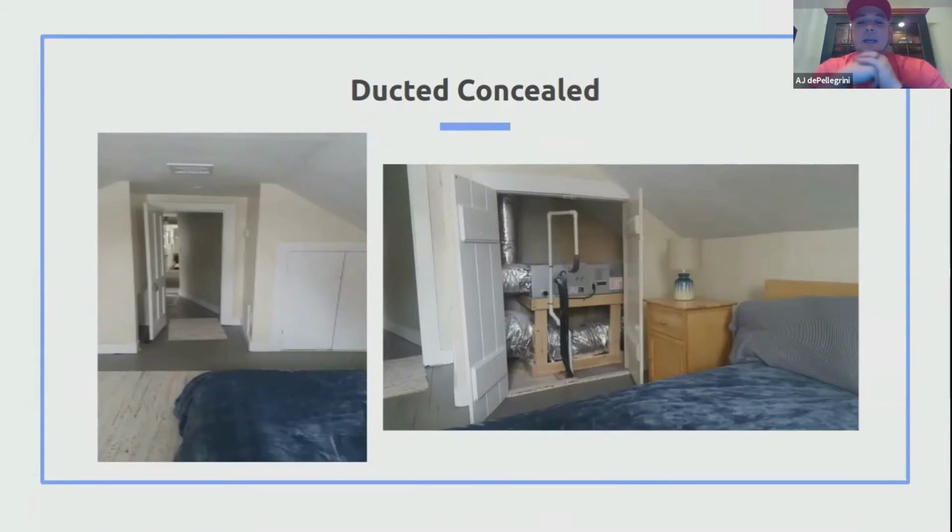This system here takes care of 3 upstairs bedrooms that are extremely hard to get to. The way that this works is a basic air handler with heat pump technology. So the coil can deal with hot or cold refrigerant, and it also works with the system. So it has variable fan speeds. It will modulate itself on refrigerant flow up or down.